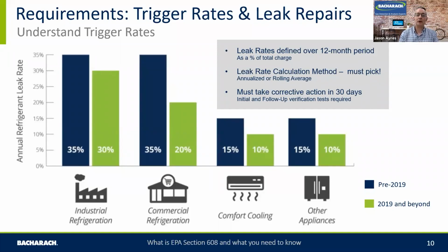So it's important you understand your assets, the grouping that they fall in under, and then when you add refrigerant to the system due to refrigerant loss, if they breach a trigger rate, you need to do something to follow up on that to prevent any further refrigerant emissions. And they're called leak inspections.